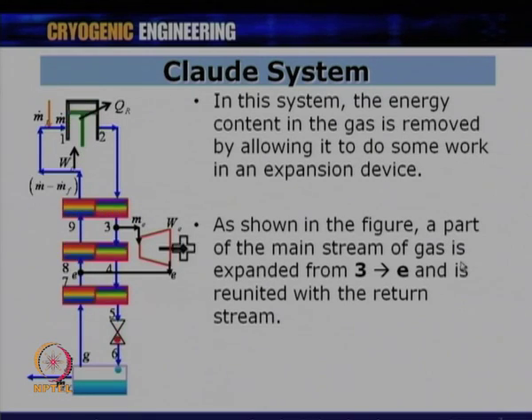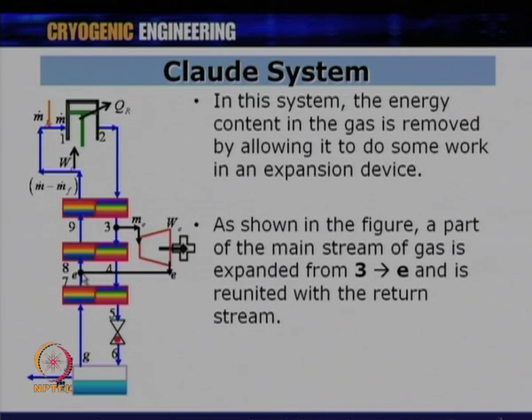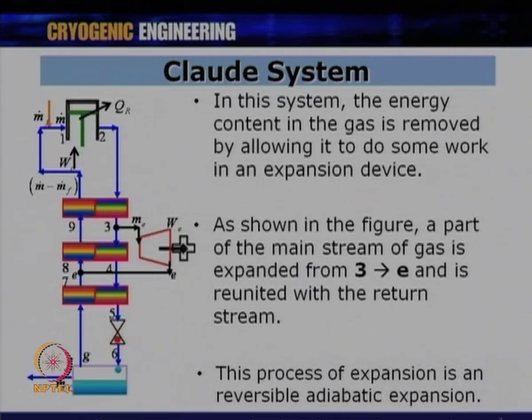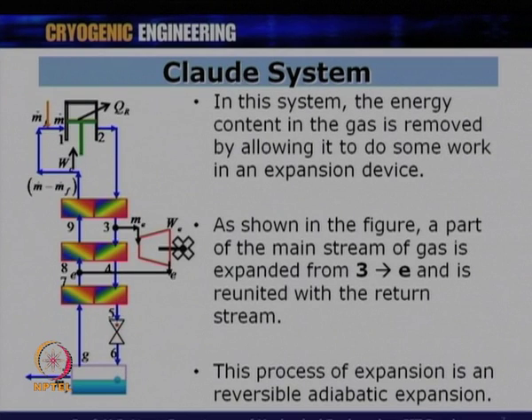A part of the main stream of gas is expanded from point 3 to point E. The gas m_e is taken from the compressed stream M, expands from point 3 to E where it joins the return stream and produces cold, after which JT expansion yields liquid. This expansion is ideally a reversible adiabatic (isentropic) expansion; we will account for real efficiency later.